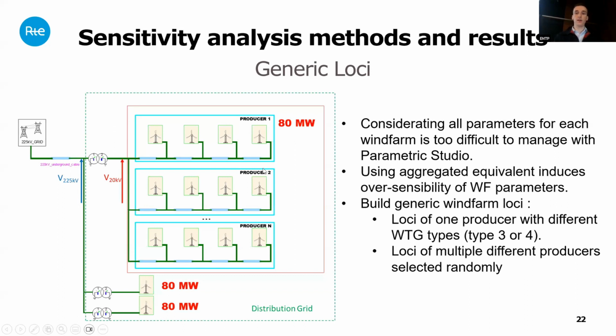For that, we compute different loci for different producers with random parameters, then connect them together on the same 20 kV busbar, and perform a frequency scan to build this overall 80 megawatt locus. We also add another parameter: the rate of type 3 or type 4 wind turbines connected to the grid.